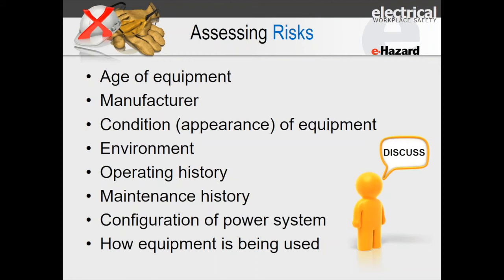potential incident energy analysis study, or the PPE category method from CSA Z462 or 70E, then you come up with a number. Let's just say the voltage 600 volts, 7 calories per centimeter squared. That could be the identified hazard for that equipment. Then it's really important to assess those risks.